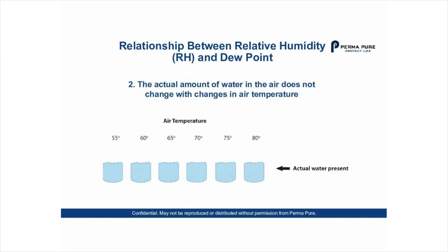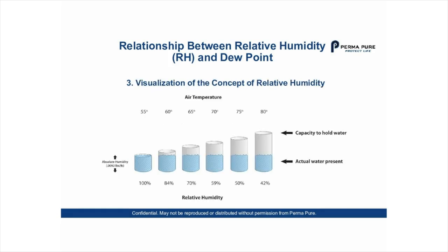The next slide shows the actual amount of water in the air that remains the same as the temperature changes. If there's water present in the air and the temperature changes, the amount of water doesn't change. Once we overlay those two together, we can see the relationship between relative humidity and dewpoint. At 55 degrees you have 100% relative humidity with that baseline, and as you increase the temperature it can go all the way down to a relative humidity of 42%. That means at a temperature when it seems wet and absolutely humid, 25 degrees above that it's going to feel dry.